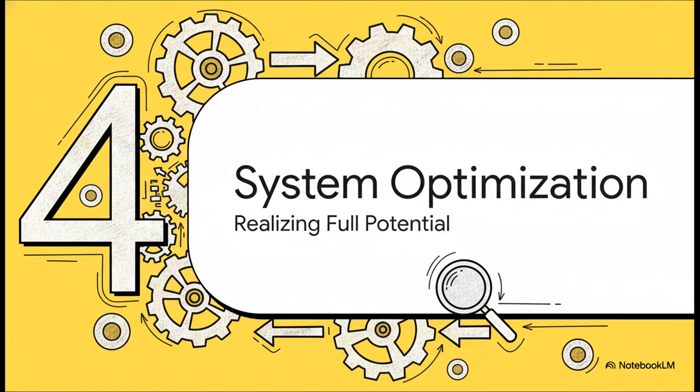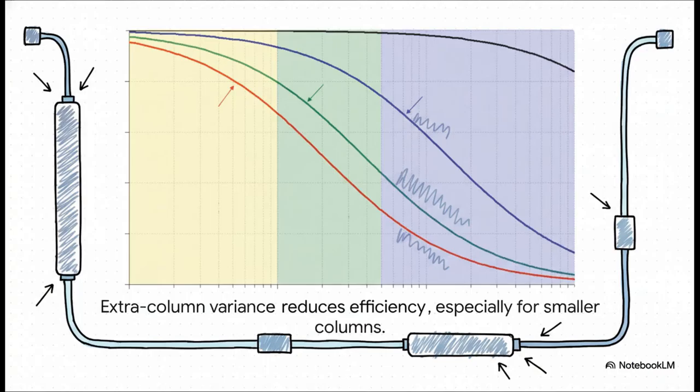Okay, so this all sounds amazing, right? But to really get all the benefits from this incredible efficiency, there is one critical thing about our system that we absolutely have to pay attention to. You see, because these columns produce such incredibly narrow, low-volume peaks, anything outside the column that adds to band broadening, what we call extra column volume, suddenly becomes a much bigger deal. We're talking about tubing, connections, the detector flow cell, all of it. To make sure you don't lose the efficiency gains you just worked for, you've got to minimize that extra volume. This is especially true if you're working with narrow-bore columns.